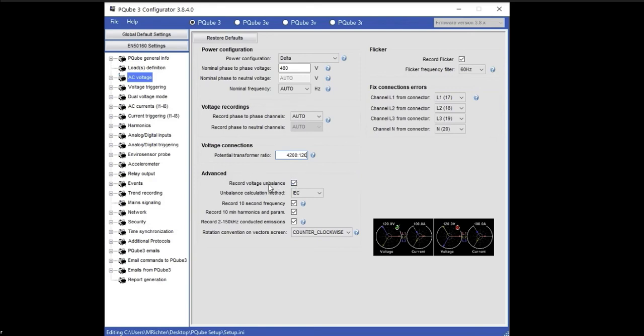The advanced features here are recording voltage unbalanced using the particular IEC method, or other methods can be chosen. Record 10-second frequencies, harmonics, record the 2 to 150 kHz conducted emissions, and which way the vectors are rotating. In California, we rotate counterclockwise. Record flicker and what flicker frequency you're operating on, 50 or 60 Hz.